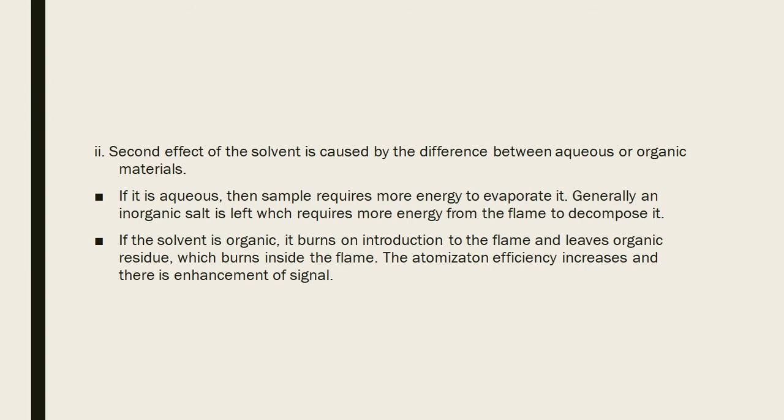The second effect of the solvent is caused by the difference between aqueous or organic material. If it is aqueous, then the sample requires more energy to evaporate it. If the solvent is organic, organic solvents are generally volatile, so they will take less time as compared to the aqueous one. So, for organic solvents, atomization efficiency increases and there is enhancement of signal as compared to the aqueous. Thus, whether the solvent is aqueous or organic will also have an effect.